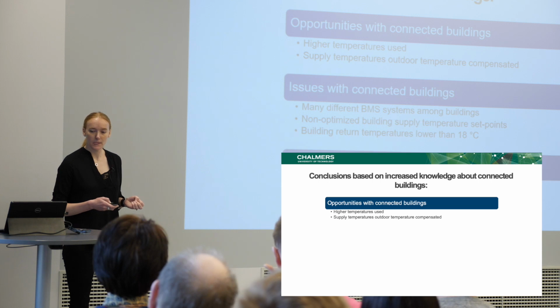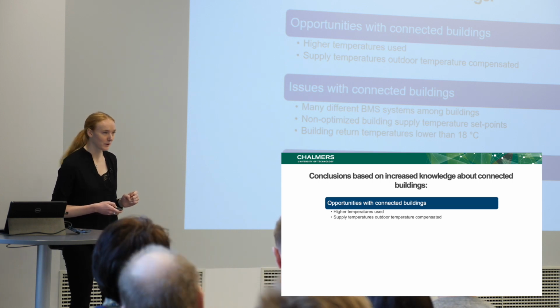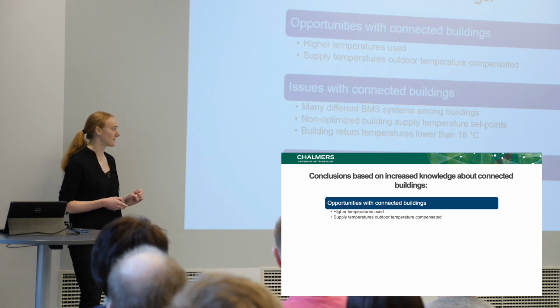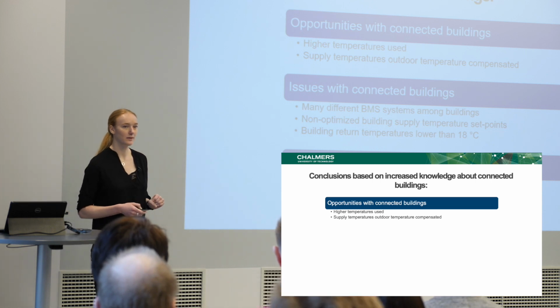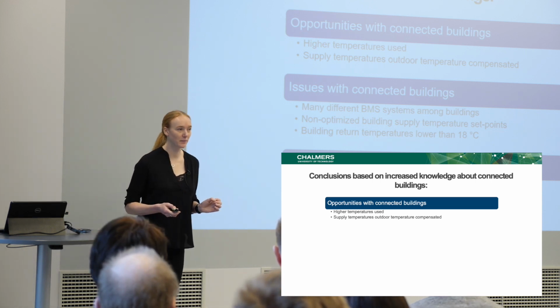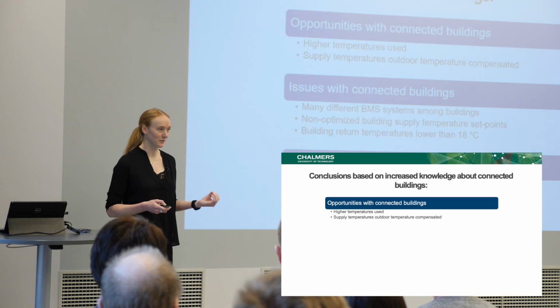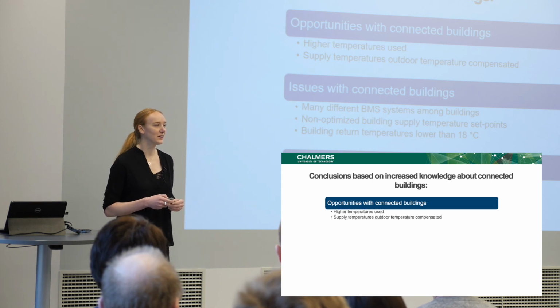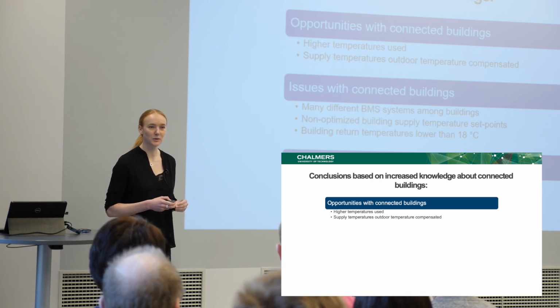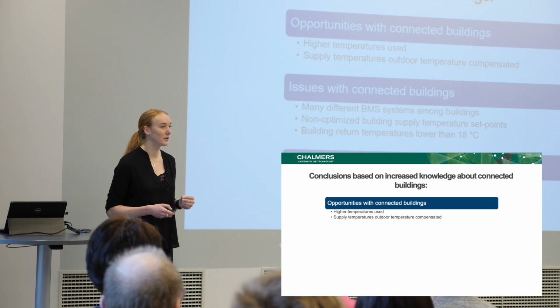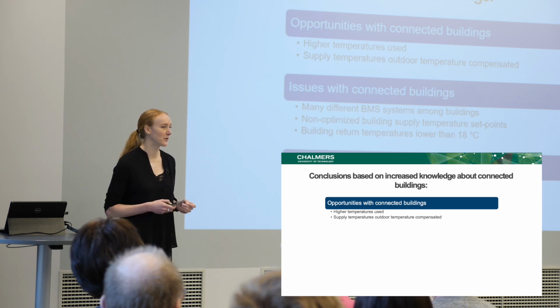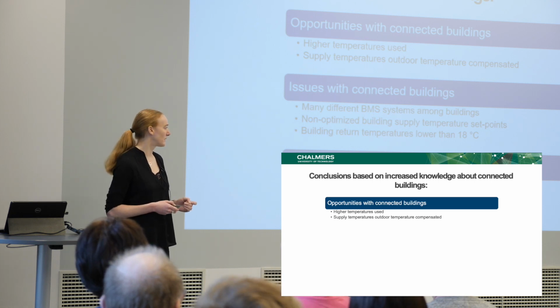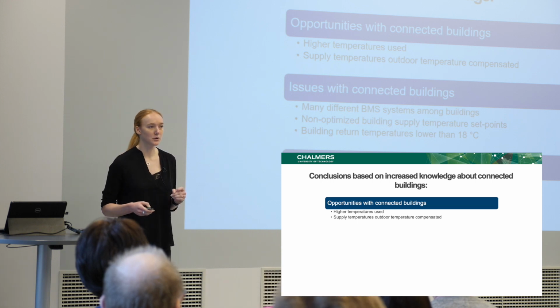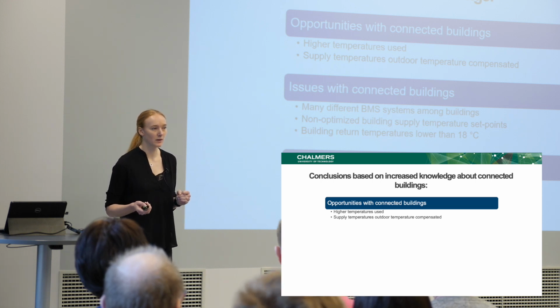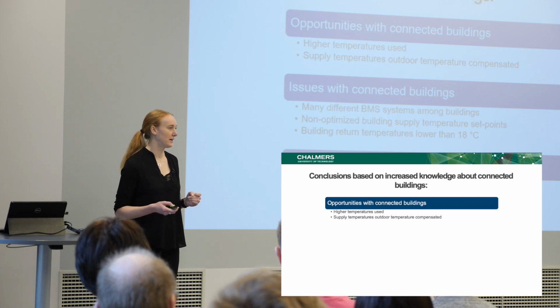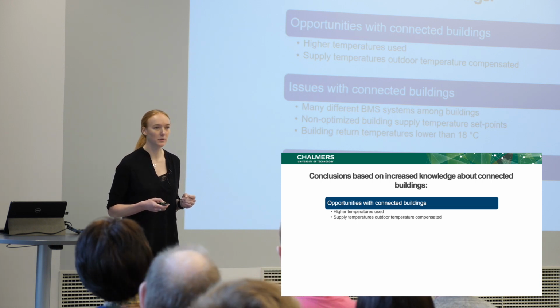Some recommendations to avoid the low delta T: it could be good to have flow restrictions on the primary side, and, as you saw earlier, not too much district cooling water should be allowed through the control valve, based on the maximum cooling power of the building. It's also important to make sure that the building set points are 2 degrees higher than the supply temperature of the district cooling water.